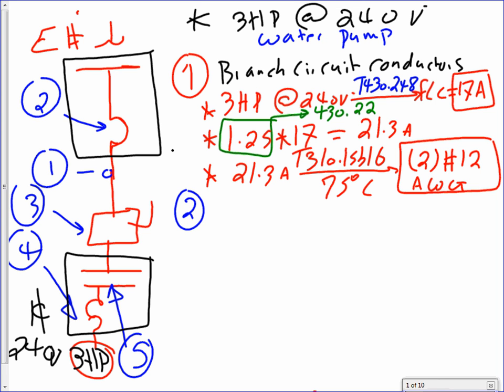Why 2 conductors, by the way? Anybody know why 2 conductors? It's a 240. Do you need a neutral? No, unless they tell you that you need a neutral. So, 2 conductors, AWG, THHW. Why do you think we use THHW? It's a wet location, so we need THHW.